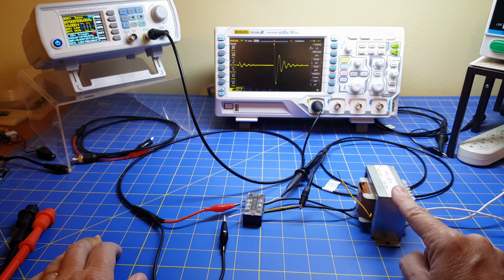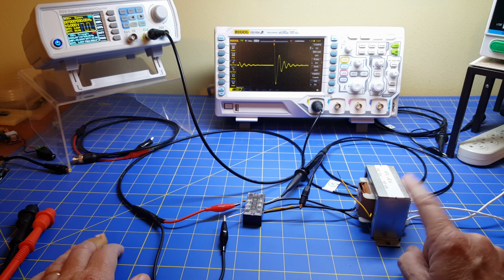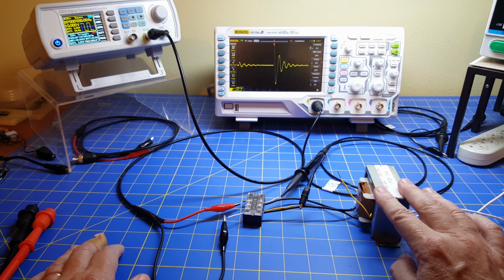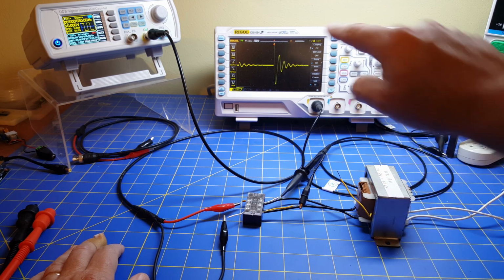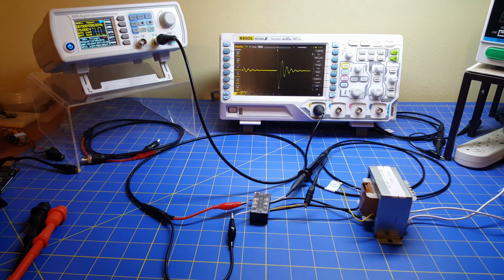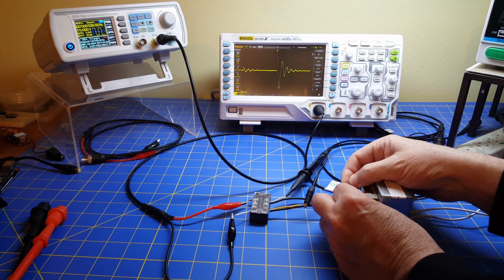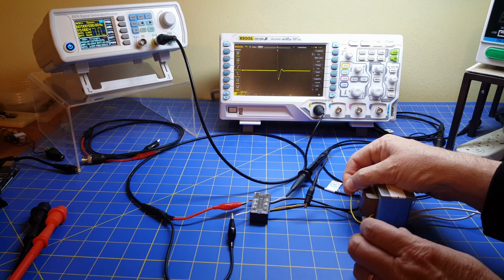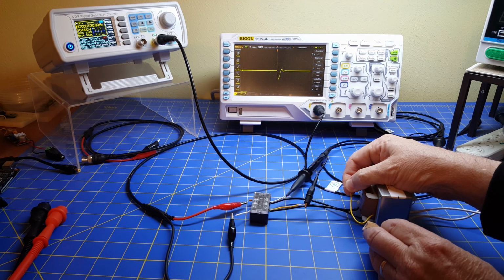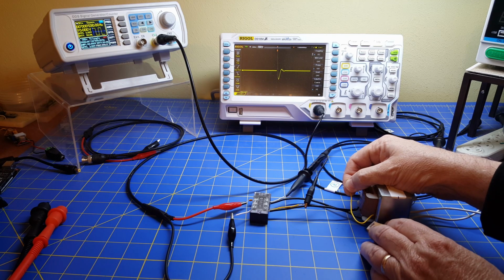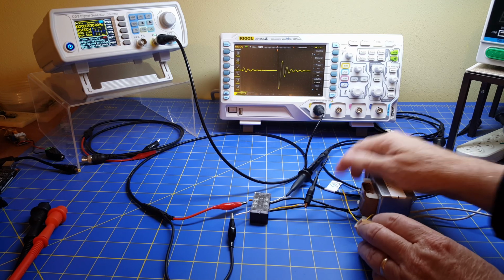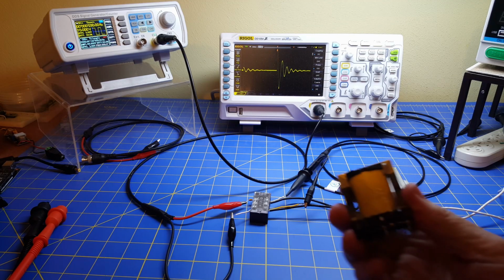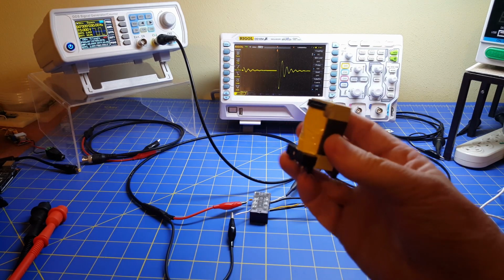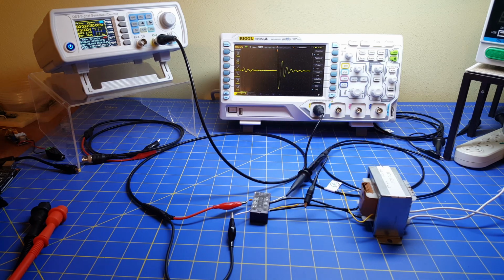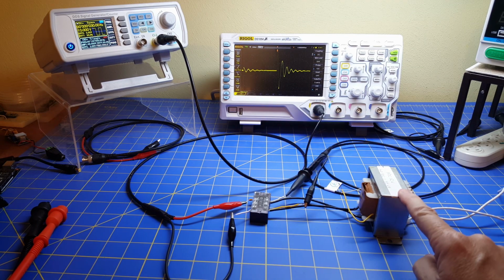Well, it turns out this is a perfectly fine transformer. Because of the characteristics of this 60 hertz power transformer, it naturally has a very damped response. Now to prove that, I can simulate a short-circuited winding by connecting this wire together, and you can see this is what a short-circuited winding might look like if it was a perfect short-circuited turn. So again, it's really difficult, if you take a transformer, to determine how many rings you expect, because it gets really, really complicated.